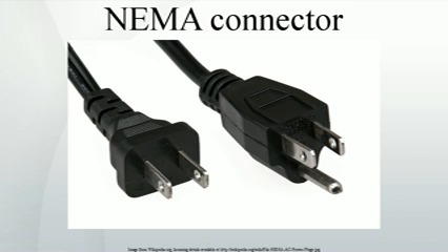6-15R and 6-20R receptacles are usually manufactured on the same assembly line as industrial or commercial-grade 5-15R and 5-20R receptacles, with all 4 receptacles sharing the same triple-wide T-contacts behind the varying faceplates. The faceplate bonded onto the receptacle determines the final configuration of the receptacle. The 30A plug and socket look similar to the 15A one but larger. The higher current versions are rare, with twist-locking plugs such as L6-30 or direct wiring more common.